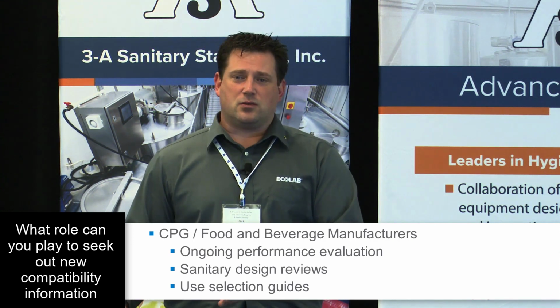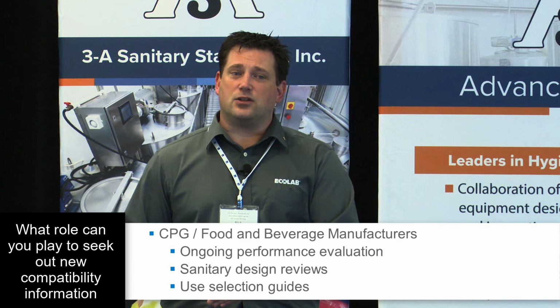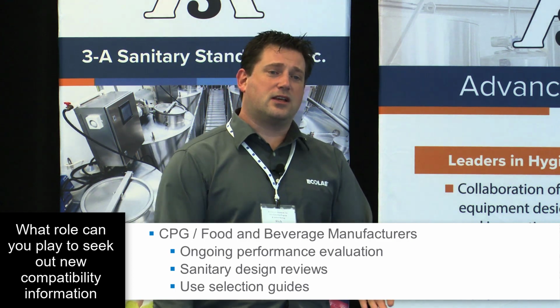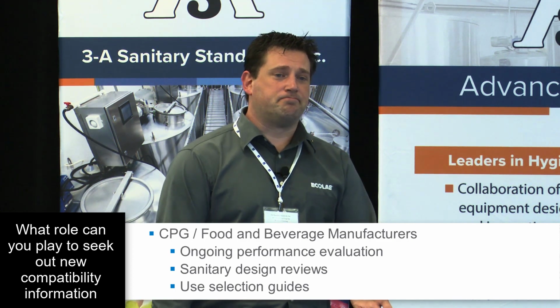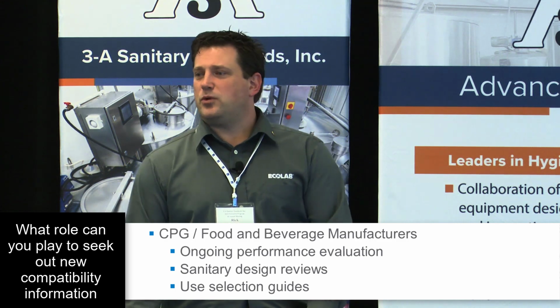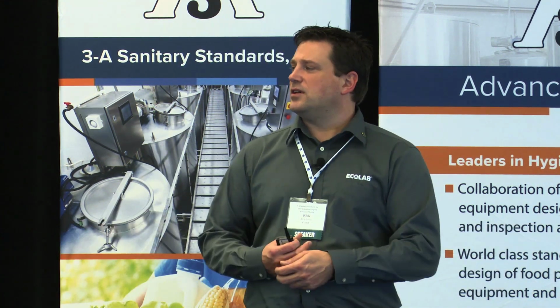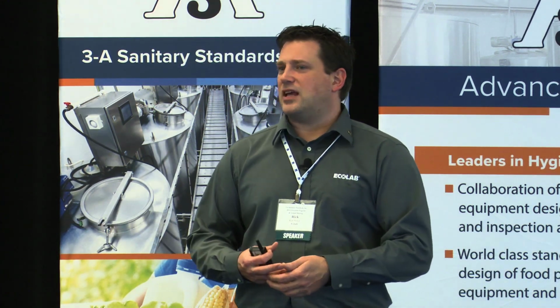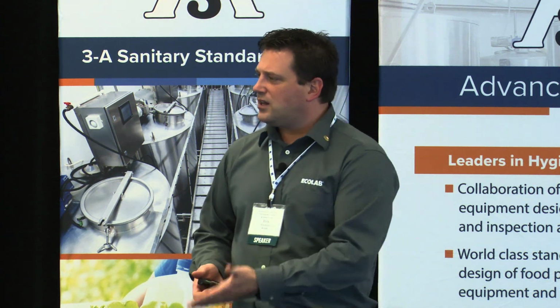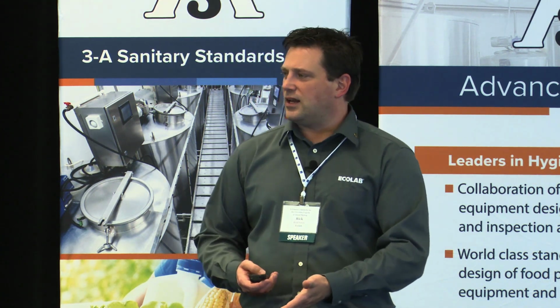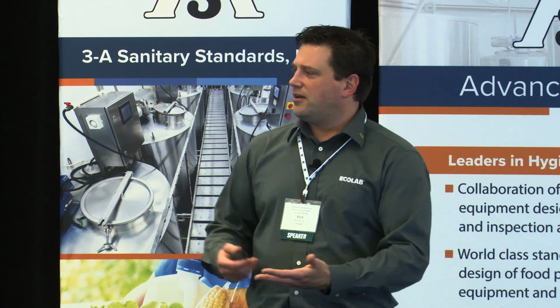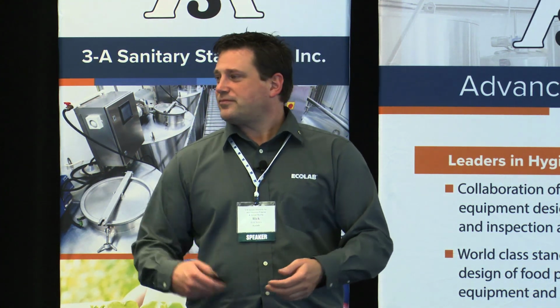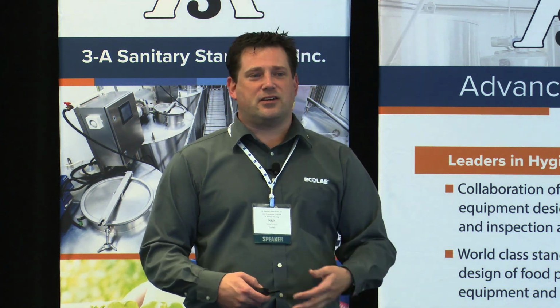Note the condition. When you go out and replace a gasket, do they note what condition the gaskets were in when they replaced them? That's a simple one that I've seen missed so often. I was like, you have this gasket replacement program, but you're not telling me what condition they were in. And I know they weren't all good. I've done a lot of gasket replacements in my time. And conduct sanitary design reviews and use selection guides.